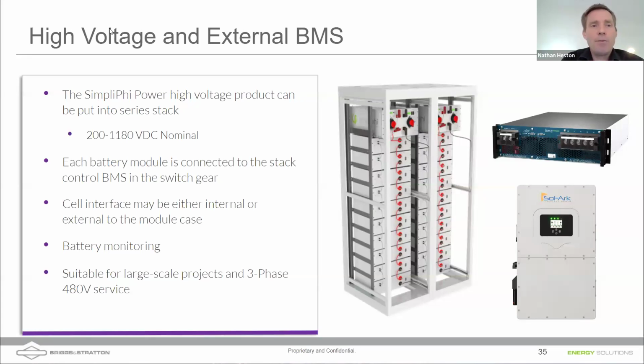Showing once again the high voltage stacks here, 200 to 1180 volts DC nominal. Keep in mind that's not the max voltage; the max voltage will go up during a high state of charge. This is the voltage at a 50% state of charge.